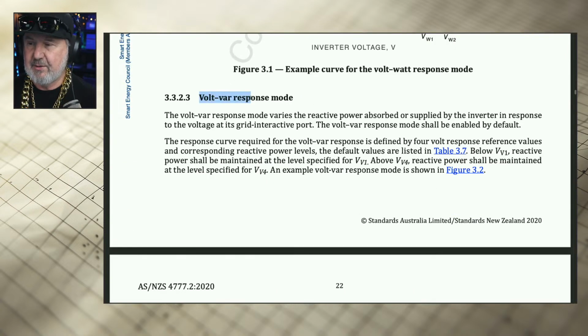But we've also got this thing called volt-var response mode. Now, once upon a time, the early versions of 4777 Part 2, way back in like 2007 I think it was, basically only had watt modes and very harsh cutoffs. As soon as you hit, depending on the inverter settings, some maximums like 253 volts in Australia, you had to switch off within 2 seconds.